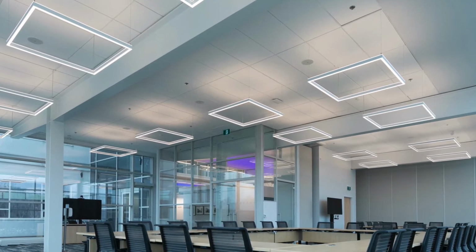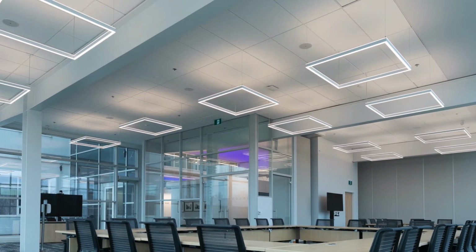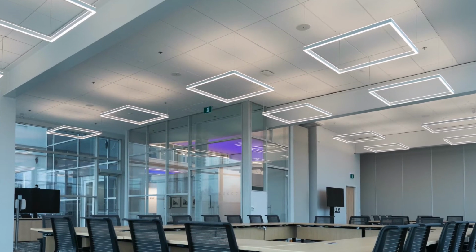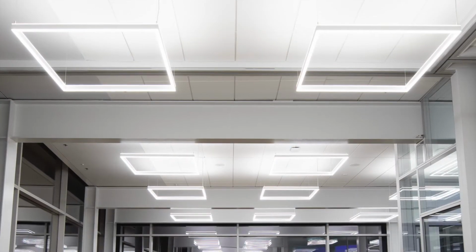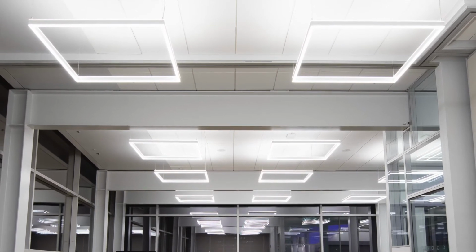Suspended luminaires are 2 circuits separating uplight from downlight. Controls provide maximum flexibility while daylight harvesting sets the maximum light output. Tuning can be adjusted in the future for lumen maintenance, increasing the useful life of the luminaires. The expandable flexible lighting control system includes daylight harvesting, vacancy sensing, and light level tuning.